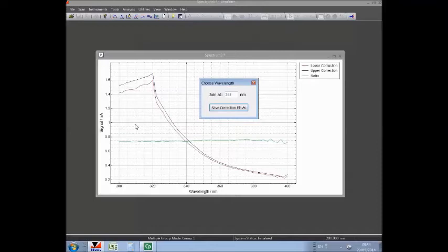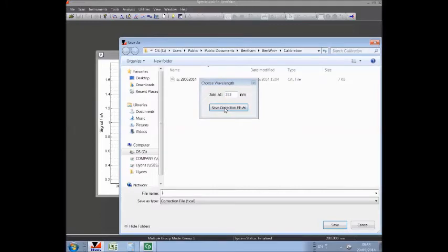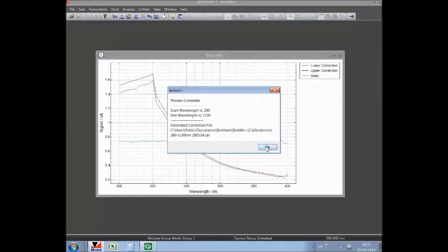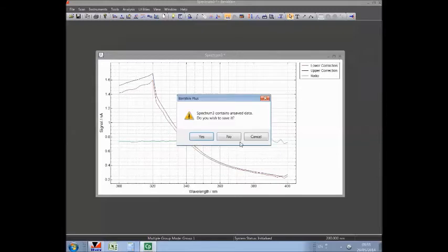This window shows the resultant calibration file for the two lamps, and the green line the ratio of the two. And we typically take a midpoint as being the crossover point. So effectively, the calibration file for the CL6 from 352 up is maintained. We adopt the calibration file of the CL7 below 352 nanometers, but adjust it to a level to match the CL6. And 352 is where the software always tends to find the best crossover point, and we can hit Save Correction File, and we'll call it Irradiance 200 to 1100 nanometers, and we can add today's date for future reference. And the process is complete, except for one final step, and we can close this without saving.